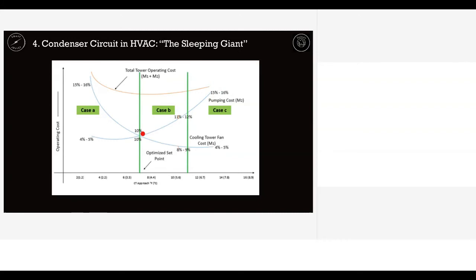So what happens is cooling tower approach is a very important parameter, that is the effectiveness of the cooling tower. Closer the cooling tower outlet temperature or the condenser entry temperature is to the chiller, the better it is for the machine. So if the cooling tower approach is low, it is very good - it's a kind of premium efficiency cooling tower having a 3 degree, 4 degree Fahrenheit, or 1 degree or 2 degree Celsius cooling tower approach.